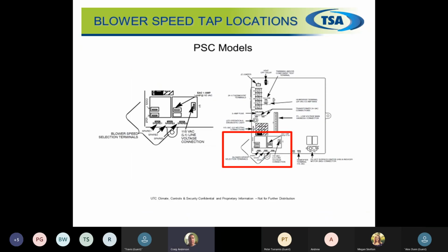So PSC motors, pretty standard on our taps to test for servicing. We have our heating, cooling tap. Some will have taps for constant airflow. 110 coming out of the board to the motor. If we're not getting 110 out of that board to the motor, then we've got a board problem. If we have 110 coming out of that going to the motor, then we have a motor problem, or we have a wiring harness problem.